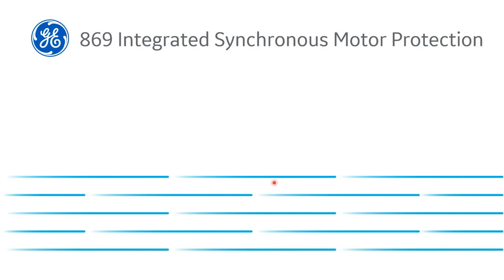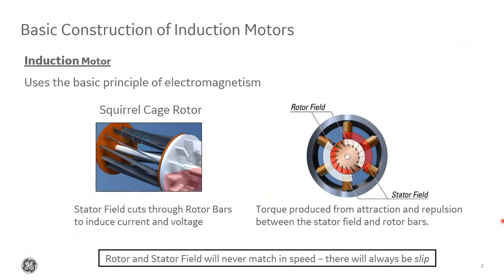Okay, so let's first take a look at synchronous motor protection. Just a quick recap of the basic construction of a motor. Here we have an induction motor, which most of you are probably more familiar with since these are much more common. An induction motor uses the basic concept of electromagnetic induction. The stator is constructed of several different windings arranged in pairs per phase, with each pair located on opposite ends and connected in series to each other. As we pass current through these stator windings, for each of these three phase pairs, the current signal on either side is at the opposite part of its cycle. And then each phase or each pair is shifted by 120 degrees.